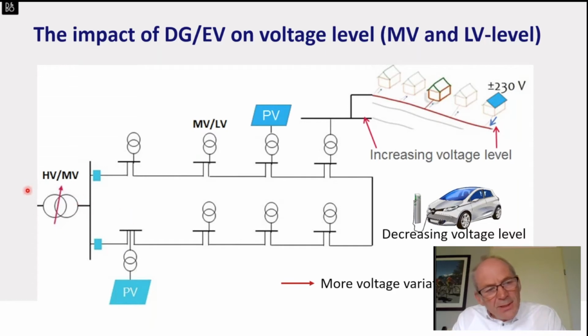At the moment there's mostly control of the voltage at the transformer from high voltage to medium voltage. Then at the end, in the low voltage network, solar systems are added, increasing the voltage level at the end of the low voltage installation, because the energy has to go back from the houses into the network or to other houses.